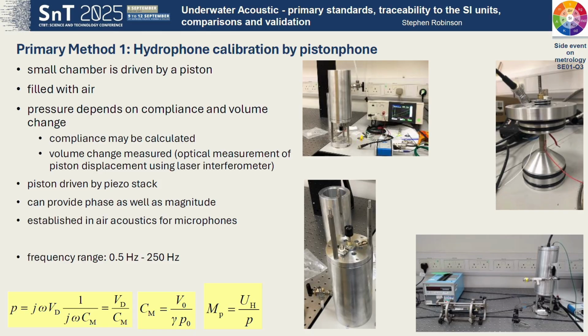For the piston phone, first of all, here we insert the hydrophone into a small chamber. We then drive that chamber with a piston. The pressure that the hydrophone senses depends on the compliance of that chamber and the change in volume caused by the piston, which we can measure because we measure the displacement of that piston using a laser interferometer. So here the traceability goes back to the primary standards of length, essentially dimensional metrology, if you like. Of course, so that we realize an acoustic Pascal using this, to be able to disseminate that, you need to calibrate a hydrophone. So you basically have to make electrical measurements. So there is some electrical traceability involved, inevitably.